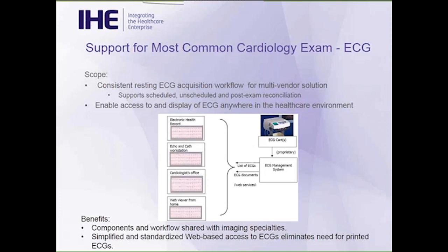The first profile is the resting ECG workflow profile, and this is leveraging the work in the cath and echo workflow integration profiles and supports handling of patient identifiers, ordering, scheduling, status reporting, and data storage. And it also addresses the need, additionally for ECGs, of having intermittently connected acquisition modalities on the network.